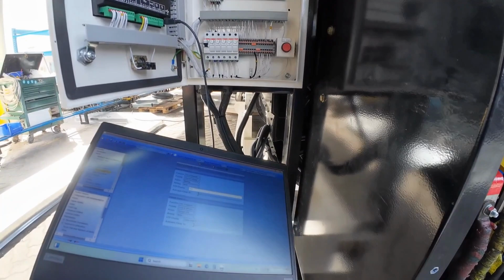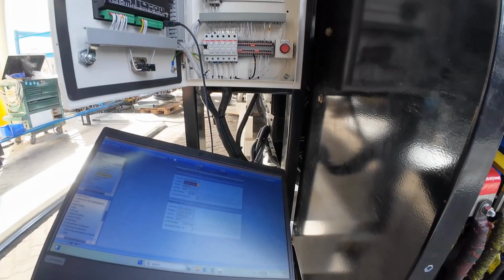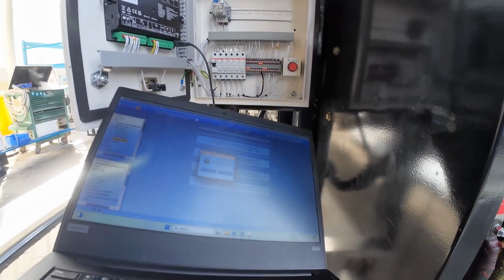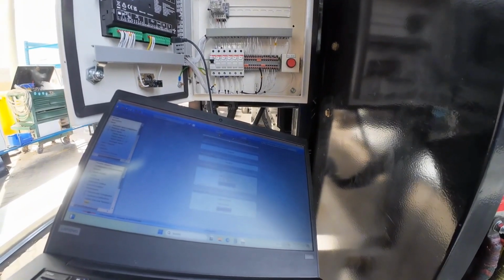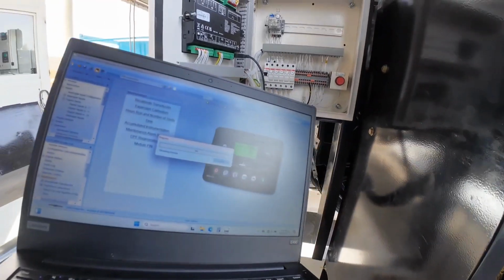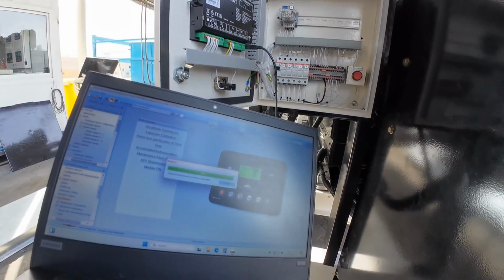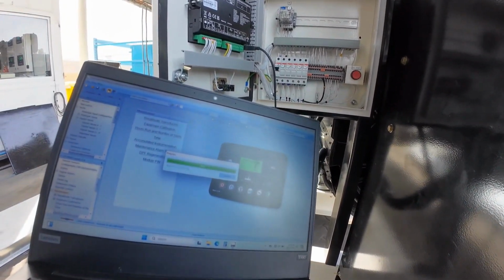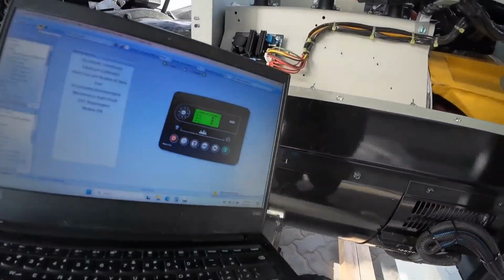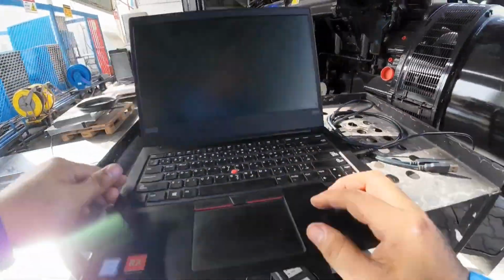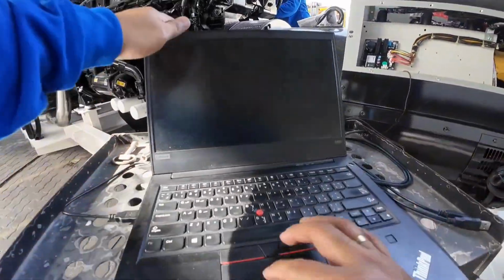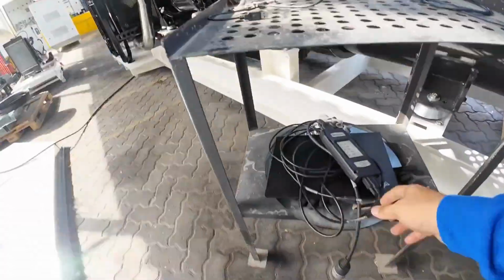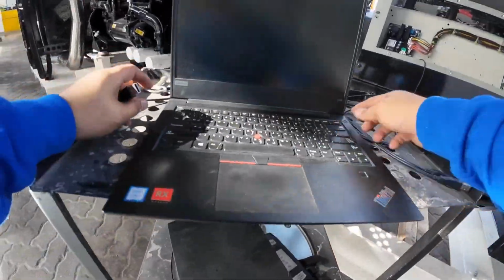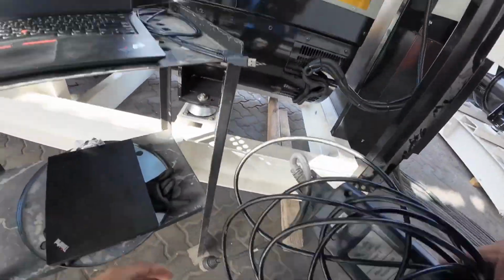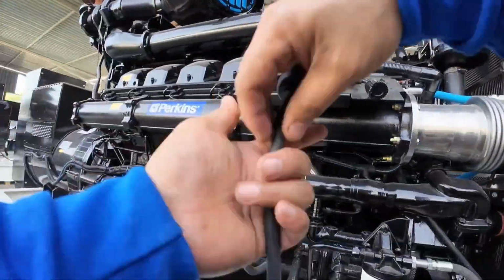I'm still checking our digital input for the configurations. I think it's finally ready, so I'm adjusting the time and writing the configurations for this module. This module is 6120, and the AVR is digital AVR D350. We need to do the configurations so it will work properly for our voltage adjustments and voltage specifications necessary for this generator, so it works as we want.